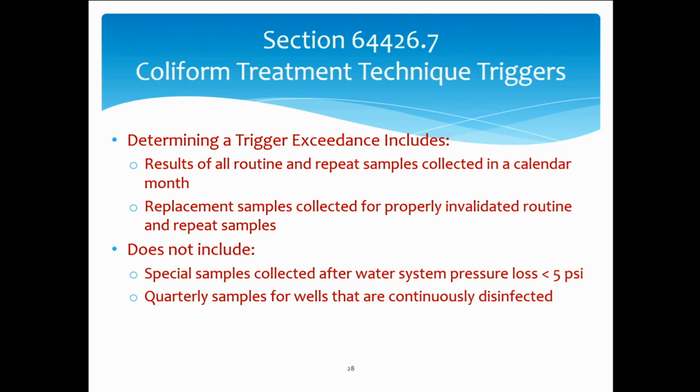Where am I? Oh, coliform treatment technique triggers. Determining a trigger exceedance includes the samples: routine and repeat samples and replacement samples. To determine if you've exceeded a trigger does not include special samples, like if your system pressure goes less than 5 psi or your quarterly raw water samples.